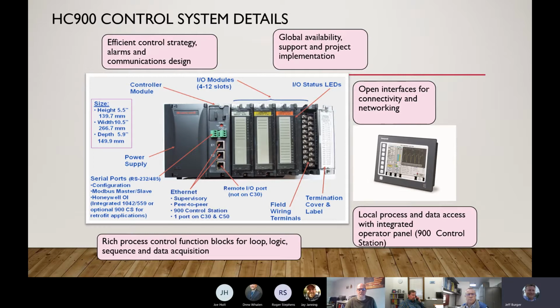The one really nice thing about those I/O modules is if you need to replace one for some reason, you can actually replace those under power. So it's a hot swap, they call it. All you need to do is remove the card, replace it with the new card, and meanwhile have your CPU up and running, and you don't have to reboot the processor when you do that. That's kind of a big thing, especially if you have a process that can't live with any downtime. Replacing I/O under power is a big thing.